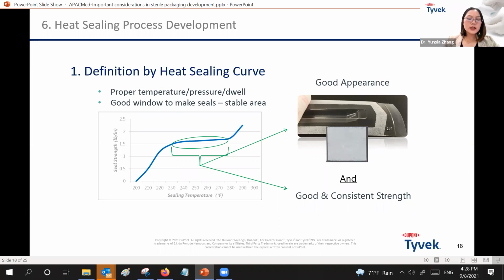So normally the peelable film supplier or coating supplier will provide a heat seal curve as a reference. And this could be used as a starting point by the sterile packaging manufacturer or medical device manufacturer to develop the heat seal curves on their specific machine. So here is an example of a heat sealing curve.